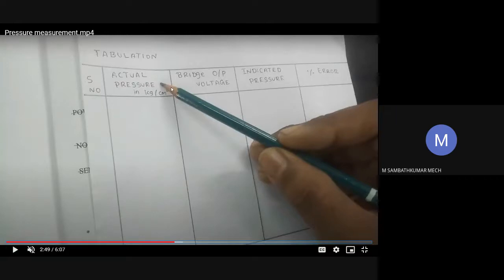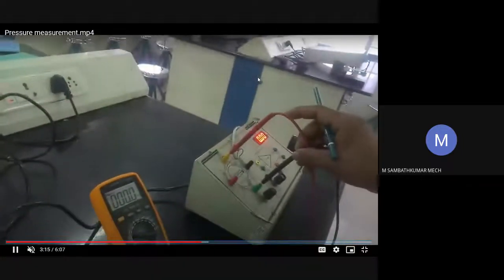In your tabular column, you are going to measure the actual pressure in your drum or compressor tank by using the pressure gauge, along with the bridge output voltage and the indicated pressure. The indicated pressure is available in your pressure measurement trainer kit. Using the actual pressure and indicated pressure, you are going to calculate the percentage of error. So this is your tabular column. Before starting the experiment, you should set 0, and only then increase the pressure by using the foot pump.